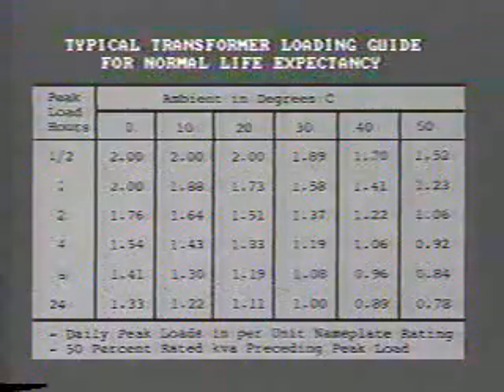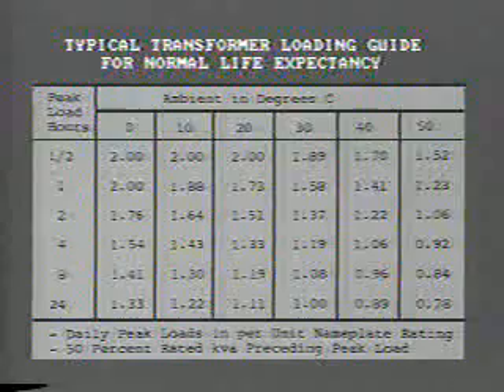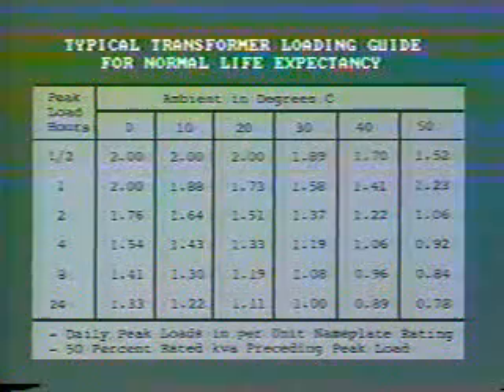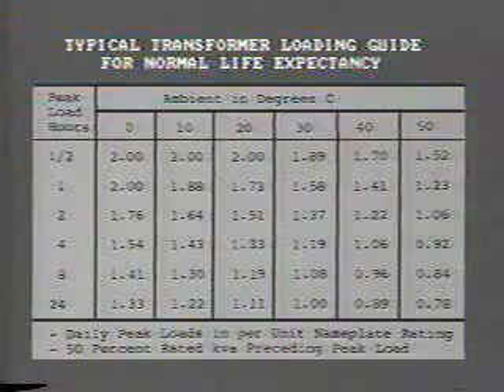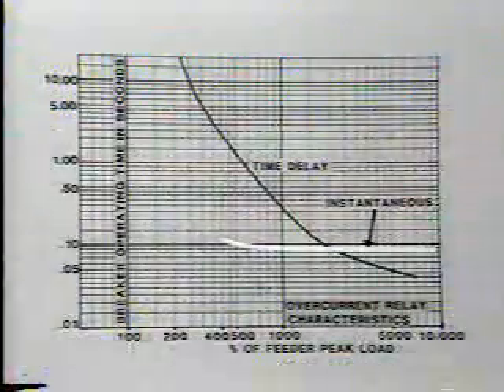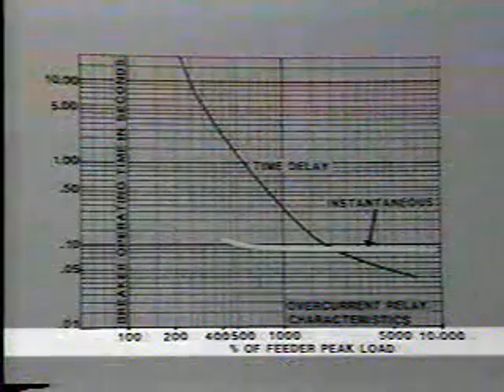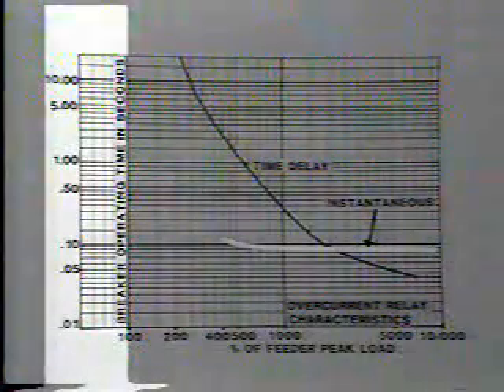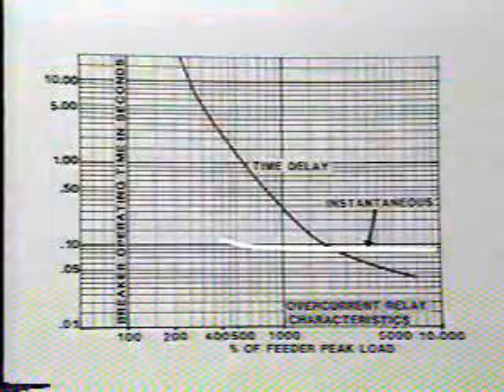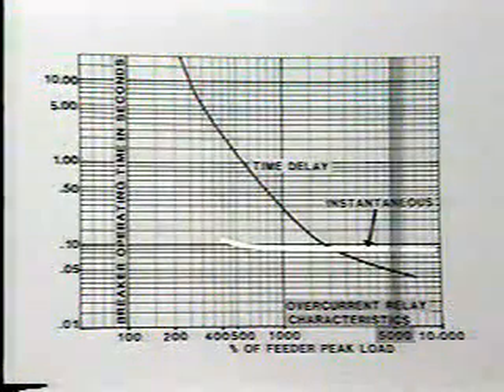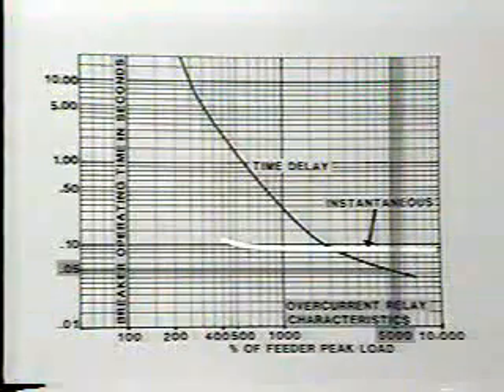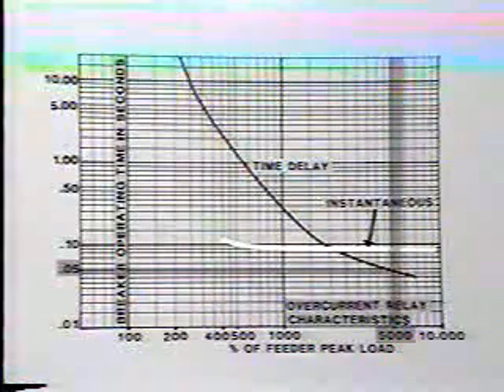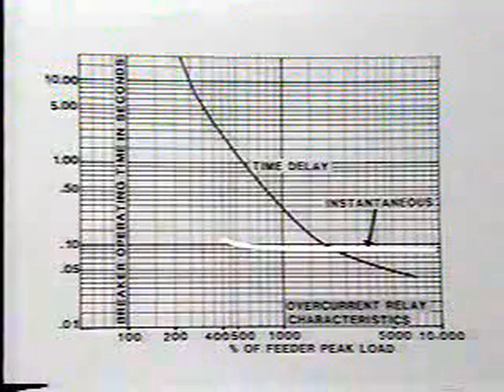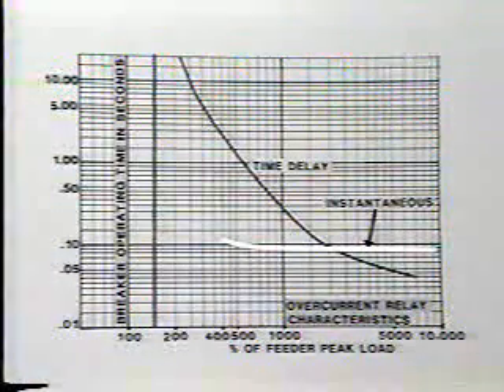We must recognize that some fault conditions may be tolerable, at least for a short period of time, but others may be intolerable and require immediate isolation from the system to prevent damage. The protective system must be able to measure and respond to its incoming signals in a very short time period. If the conditions are determined to be intolerable, then the protective system must take action immediately, usually to trip out circuit breakers. Conversely, if the fault is tolerable, then the protective system must not operate.